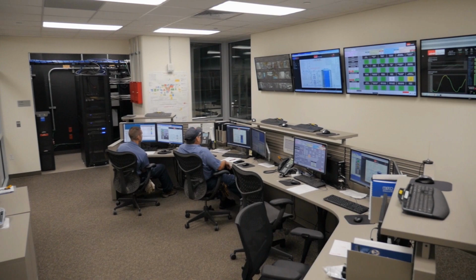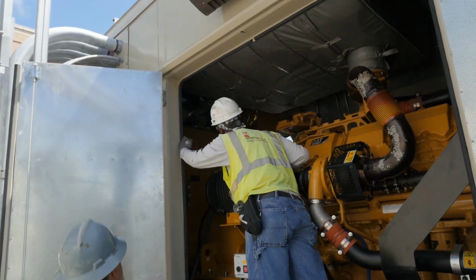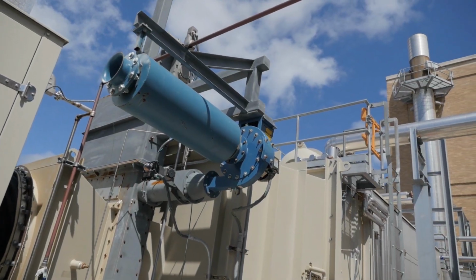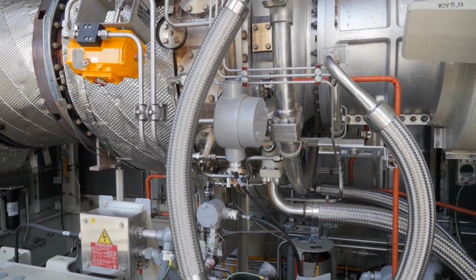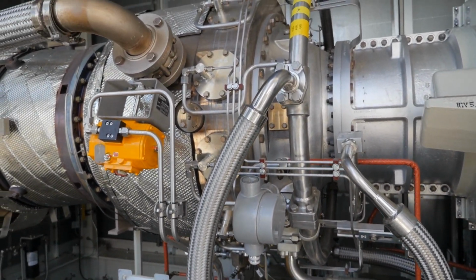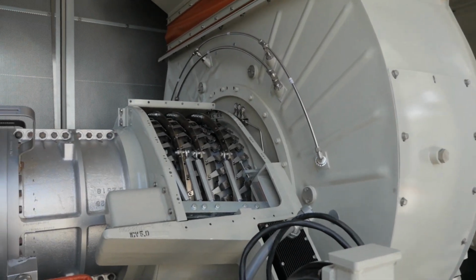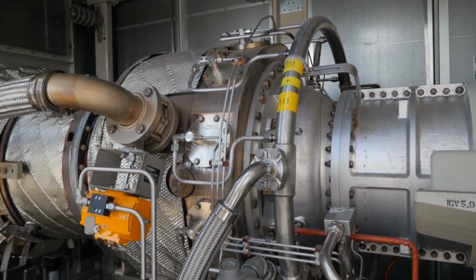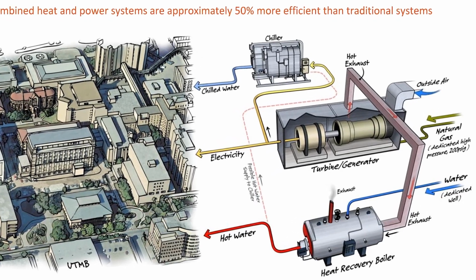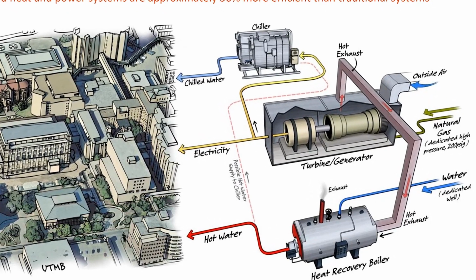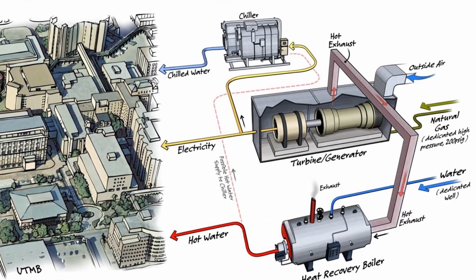We are now at the stage of that plan where we have the 15 megawatts worth of generation in place. We've actually just gone through the first real test of that system in Hurricane Harvey. It proved a number of the elements of the design that we hoped it would. We proved the ability to switch fuels. We lost municipal electric supply. We were able to continue using our self-generated electricity on natural gas. That fuel switching is exactly part of the plan and worked very well for us.